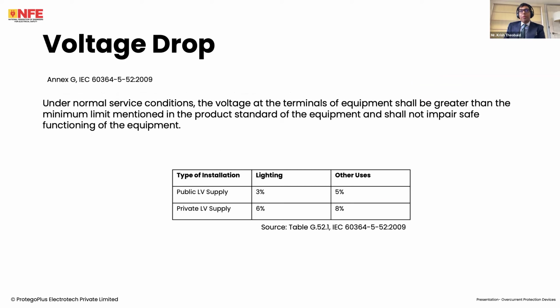Voltage drop, like I said, under normal service conditions, the idea is that the voltage at the terminals of the equipment shall be greater than the minimum limit provided in the product standard. Now, you will see in distribution systems, we also don't want to exceed the maximum limit. The standard says, in absence of this information for a public LV or any specific information for the equipment, a public LV supply, we can only allow 3% voltage drop for lighting, 5% for other uses such as power. A private LV supply, 6% for lighting, 8% for other uses.